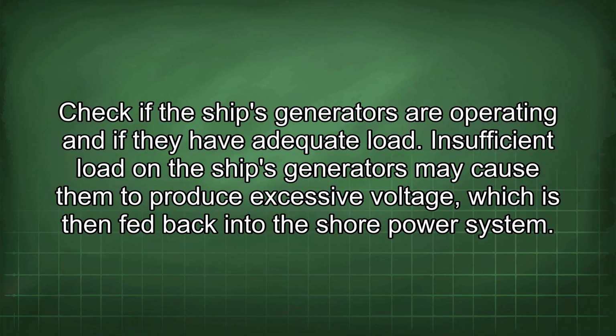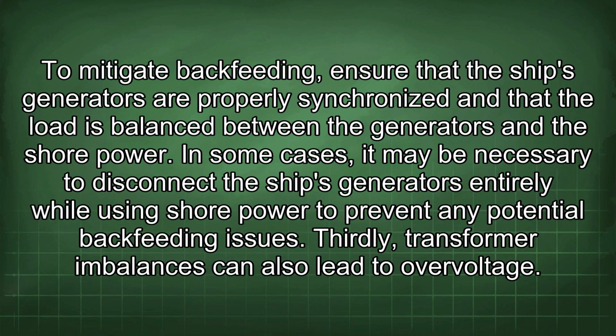Insufficient load on the ship's generators may cause them to produce excessive voltage, which is then fed back into the shore power system. To mitigate backfeeding, ensure that the ship's generators are properly synchronized and that the load is balanced between the generators and the shore power. In some cases, it may be necessary to disconnect the ship's generators entirely while using shore power to prevent any potential backfeeding issues. Thirdly, transformer imbalances can also lead to overvoltage.